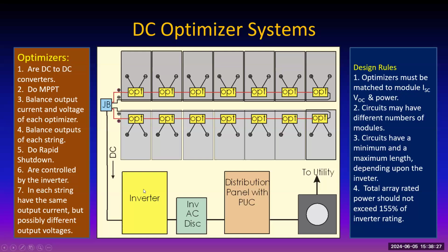Okay, and the main thing is that the total array rated power should not exceed 155% of the inverter's rating itself. Most of the time the modules don't operate anywhere near even 80% of their rated power, because they get hot and clouds are coming over, the sun's not shining directly, whatever the case. But that doesn't mean they don't put out the promised annual kilowatt hours. That's what we're paying for here. And so there's a limit to the total power of the array, because the control functions of the inverter have limits of voltage and current.